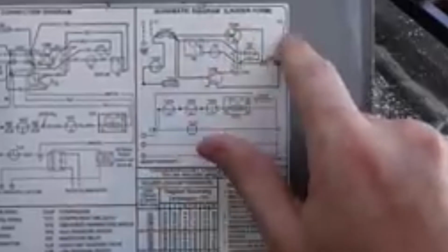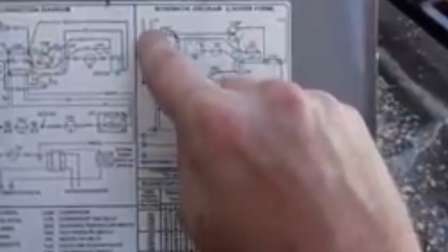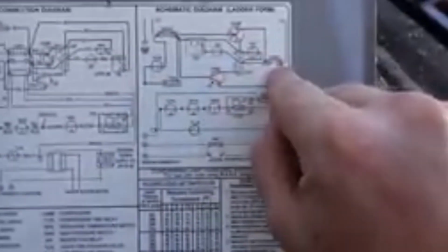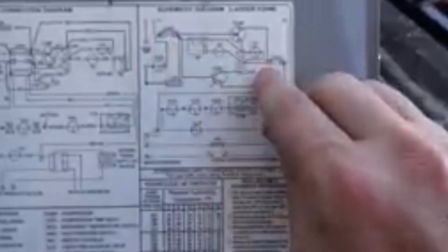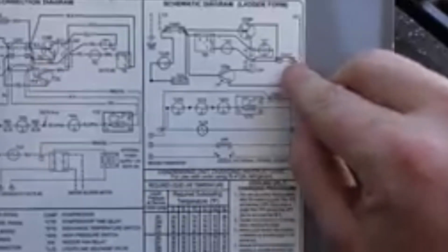In the case of our schematic ladder diagram, you can see this is our ground reference, and this is our L1 coming into the contactor, as well as our L2 coming into the other side of the contactor. We check these to each other to confirm for 240 volts. For a safety check, we check from here to ground as well as from here to ground to ensure that we don't have any potential that could cause an electrical shock.